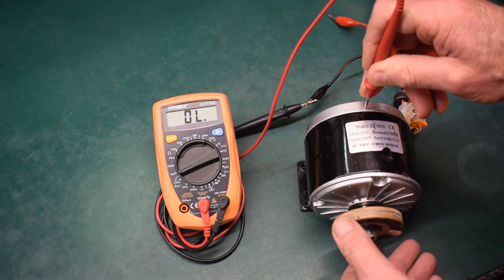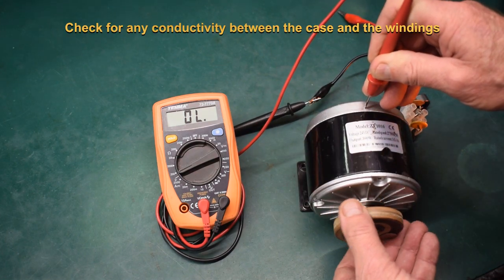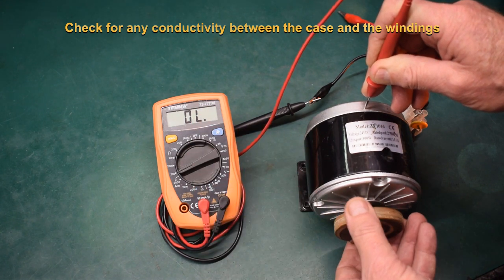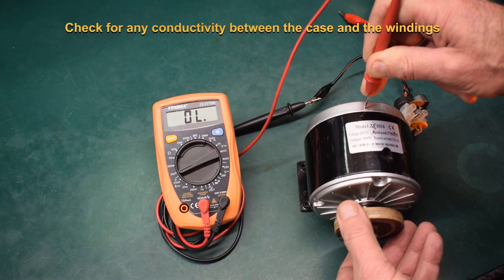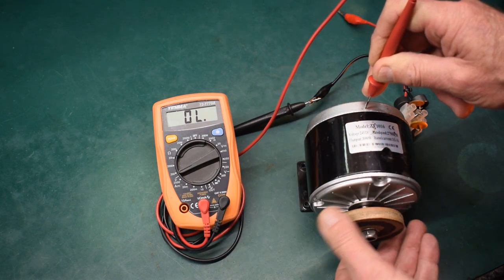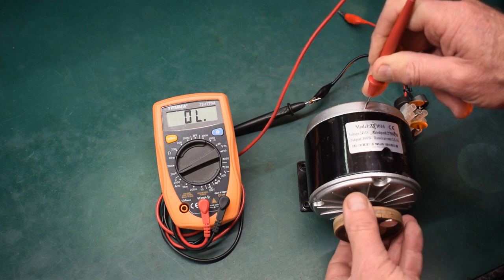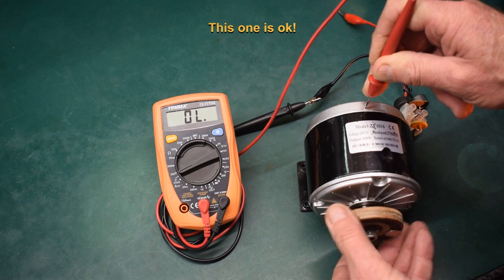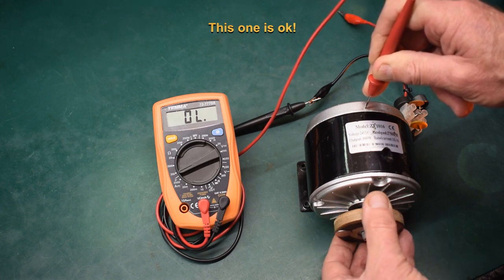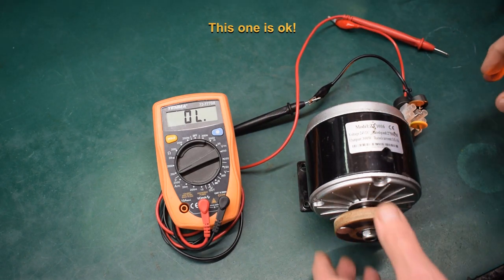Again we're going to rotate the motor through one revolution and we're looking for any conductivity between the case of the motor and the windings. You can do this one a little bit faster. Get that all the way around back to start and no continuity detected there, so that motor is okay.